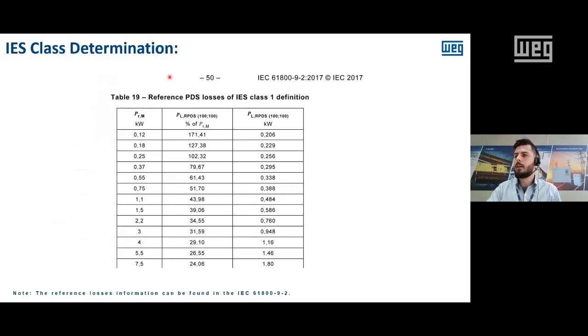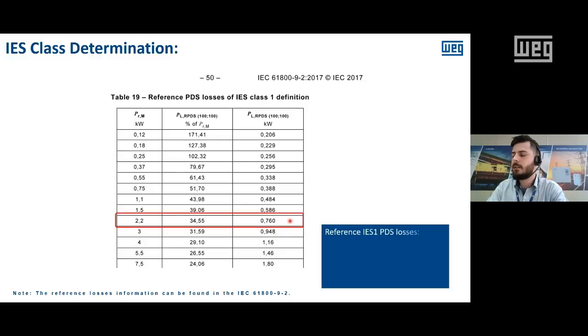Okay. In the standard, we don't have these values in the regulation, but we have them in the standard IEC 61800-9-2. And these values work with the same principle. If you have a motor, you're going to find the power rating of the motor, 2.2 kilowatts in our example. You are going to have the reference losses here in percentage and here in absolute values. So here, the reference says that the losses of the reference are 760 watts.